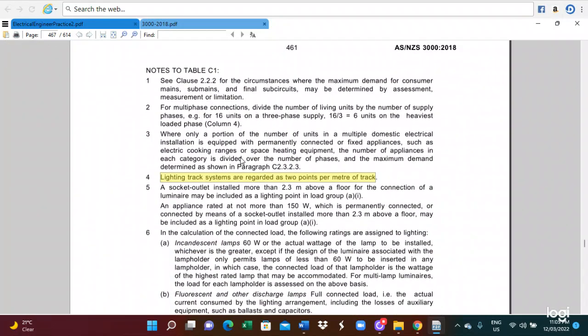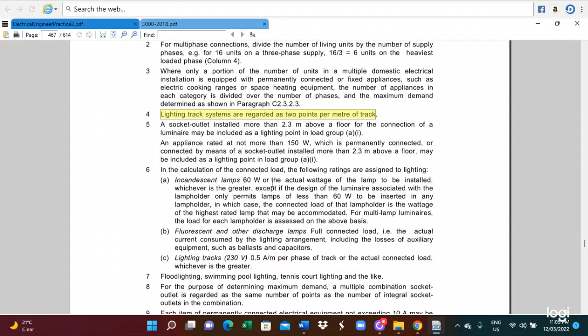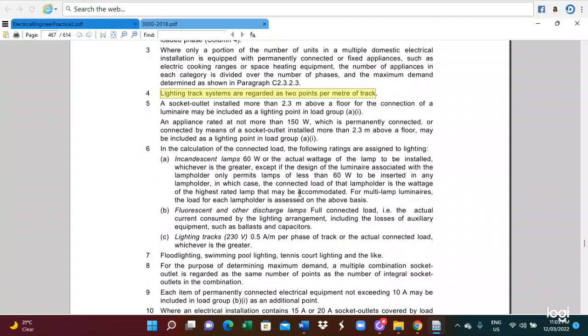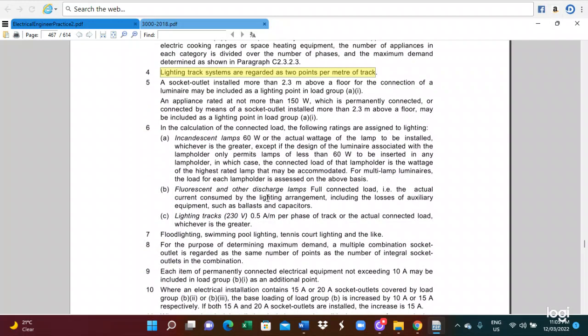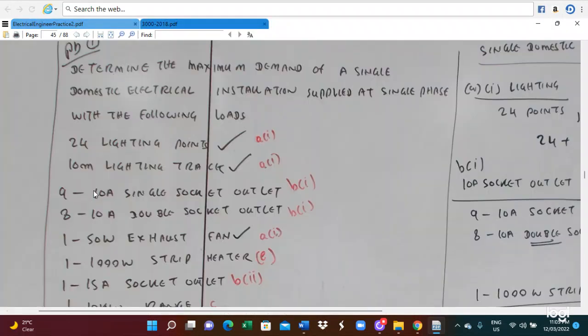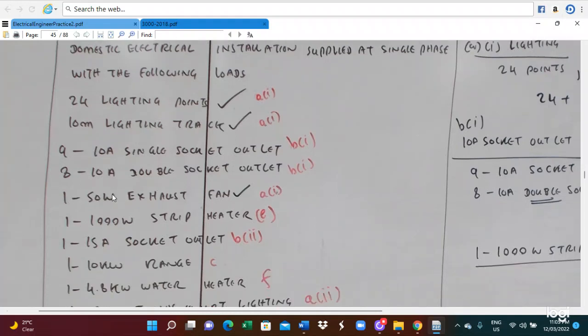Note 6 is an incandescent lamp up to 60 watt. So any incandescent lamp, we can take the 60 watt, or the fluorescent lamp, and also others with other power less than 60 watt. So any lamp holder with power less than 60 watt, we can also consider as a lighting point. This problem gives the 50 watt exhaust fan. Its power is also less than 60 watt, so this 50 watt exhaust fan is also counted as a light point.